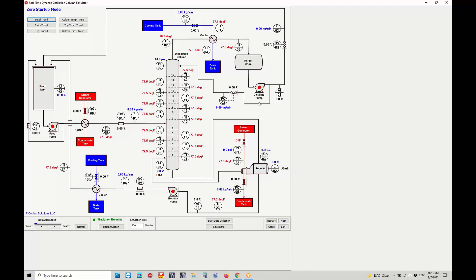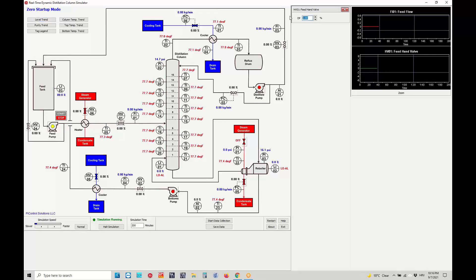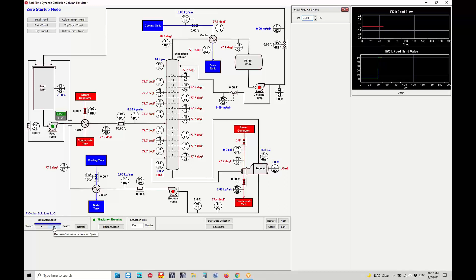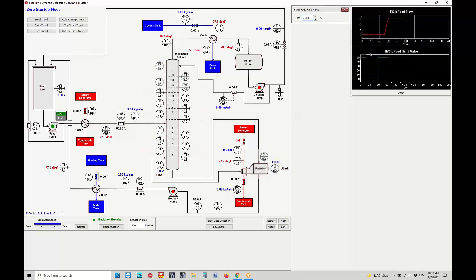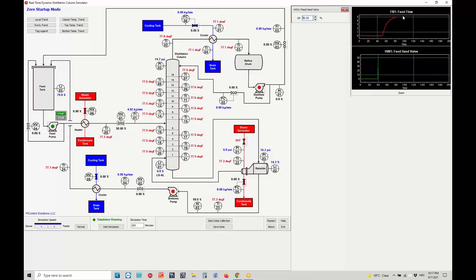In order to start up this distillation column simulator, the first thing we need to do is start the feed pump, make it start — it will turn from red to green — and then we need to open the control valve and set it to 50%. The green line on the trend shows the control valve behavior, bumped from 0 to 50%. We will also increase the simulation speed, and you will see that feed flow goes up to approximately 5 kilograms per minute, which will slowly fill up not only the distillation column level but also the reboiler level.